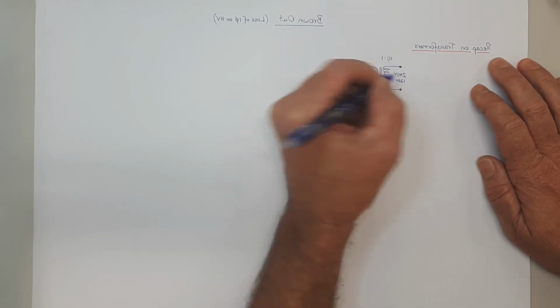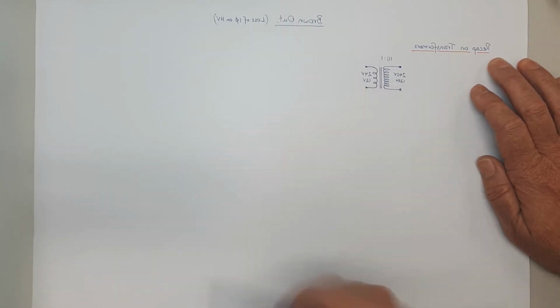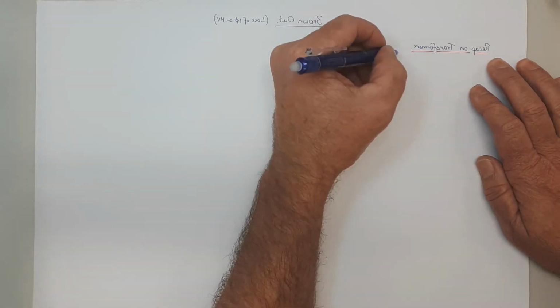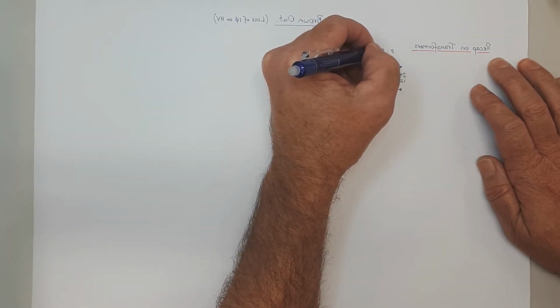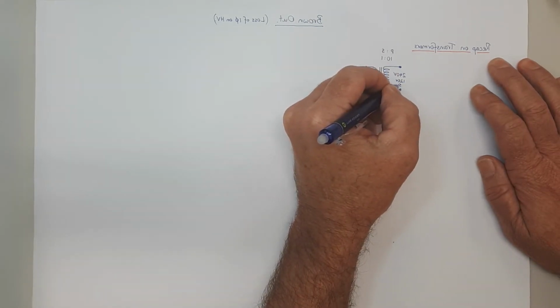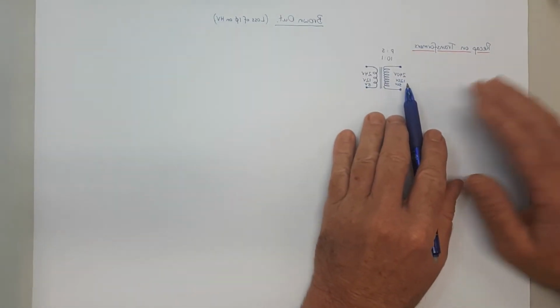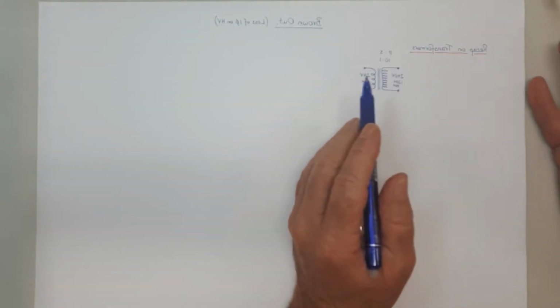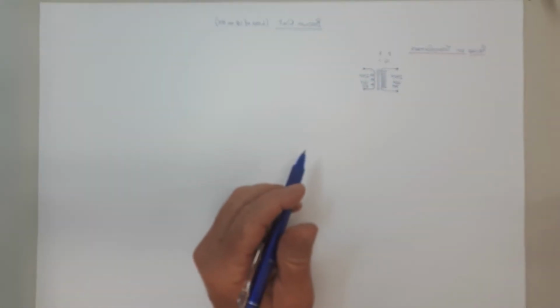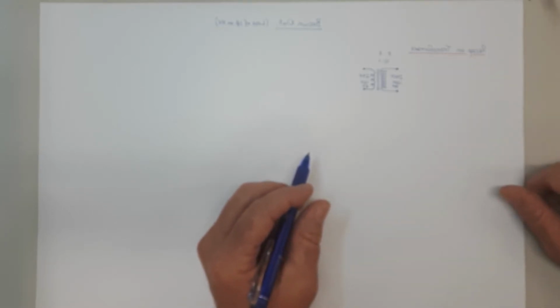But of course, if you put 120 volts on here, you will only get 12 volts on here. Whatever you put on this side, you'll get 1/10 on the secondary. Okay, I'll distinguish that, P to S. And likewise, if we put 50 volts on there, we'll get 5 volts out. You can think of any number. It doesn't work so much if you start to go above the 240. It'll still work, but there'll come a point where you've exceeded the voltage rating on this side, and you'll probably blow it up. The insulation won't be rated for the higher voltage you put on, and so there's a problem, of course.